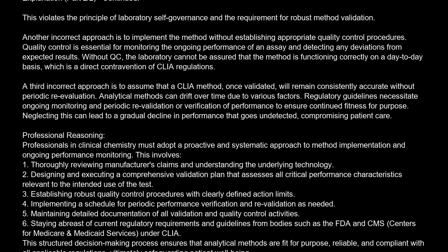Another incorrect approach is to implement the method without establishing appropriate quality control procedures. Quality control is essential for monitoring the ongoing performance of an assay and detecting any deviations from expected results. Without QC, the laboratory cannot be assured that the method is functioning correctly on a day-to-day basis, which is a direct contravention of CLIA regulations.